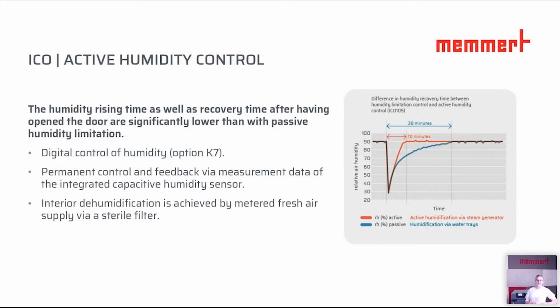And on the graph on the right-hand side, we are basically seeing the process of having opened a door with a black line. And the blue line resembles our passive humidity control. We see that the necessary and wanted percentage of 80% humidity is being achieved quite quickly, and the full recovery process takes a time of 38 minutes. Comparing this to our active humidity control, however, highlighted in orange, we can see that the complete recovery time with this option is only 10 minutes, which is quite impressive.